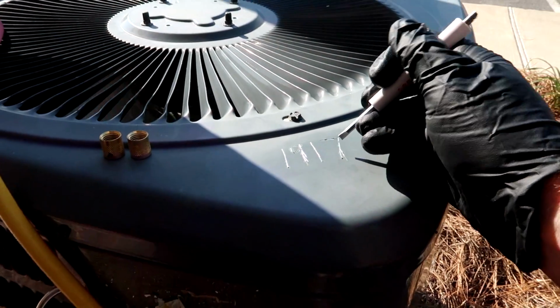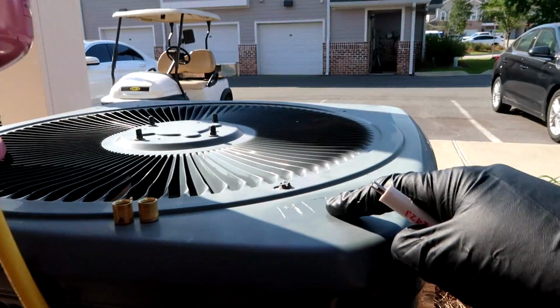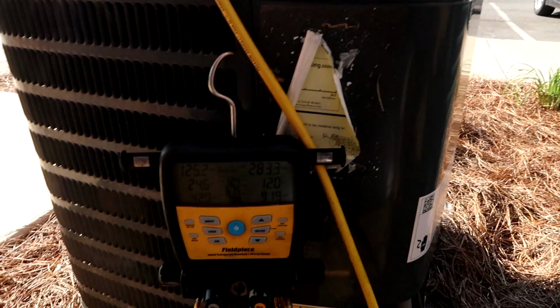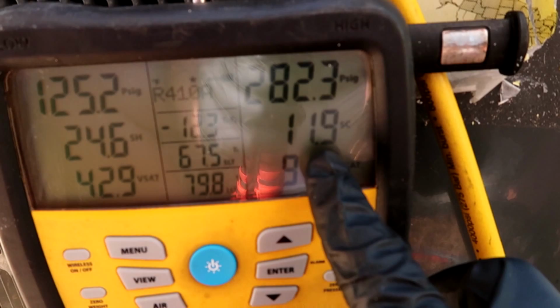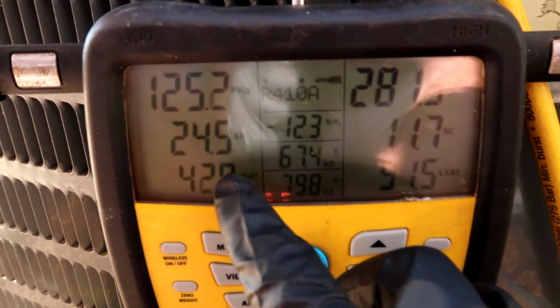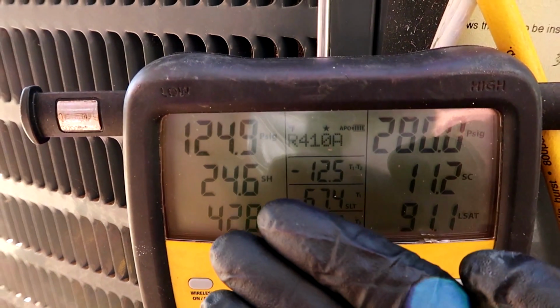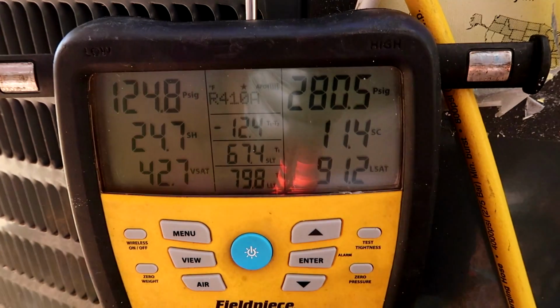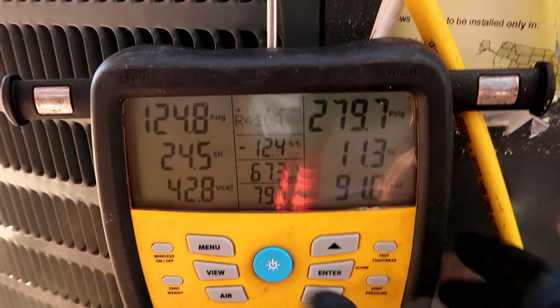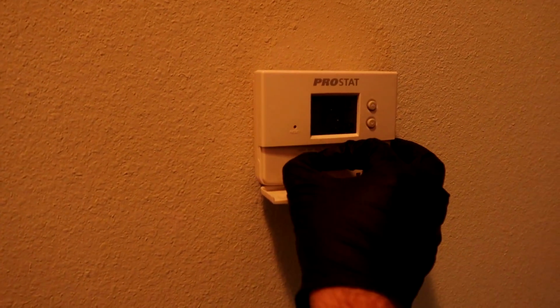I like to get my little screwdriver and engrave these things. That don't wash off like a marker does. That will rust and will never go away. Nice and labeled. All right, I got this baby at 12 degrees subcool. Around 12 degrees subcool. Once again, it is a rotary compressor. Can't get them below 20 degrees on the superheat, like I've said in the previous videos. But I bet up at the coil it's around 19 degrees or so. So, hey, I just deal with it. I didn't build the place. Now let's go look for the leak. All right, now we're back in the apartment. Let's turn the unit off and look for the leak. I'll put a filter in there when I do the charge because it can get wonky if you don't put the filter in.